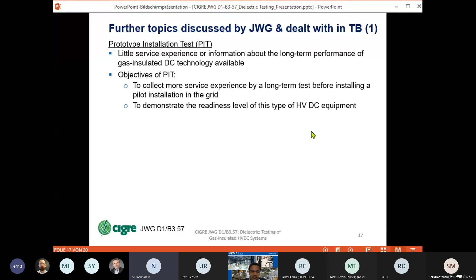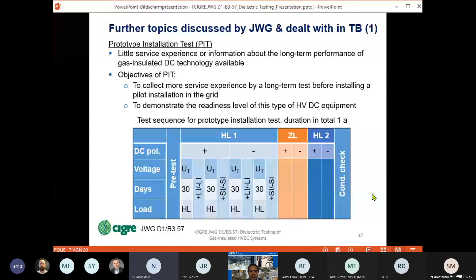The test sequence given here is similar to what you have seen before: 3 sequences, 2 high load sequences and 1 zero load sequence. In this case, the high load sequences are subdivided into different subsequences, and after each subsequence, either a lightning impulse superimposed voltage or a switching impulse superimposed voltage is applied. Finally, a condition check will be carried out.